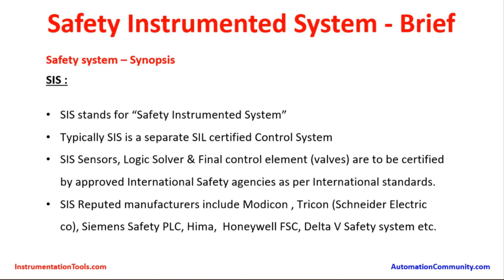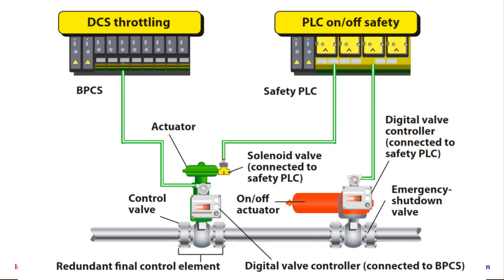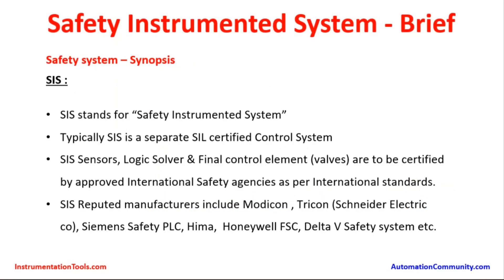I will go over the synopsis of the SIS system. SIS stands for safety instrumented system. Typically, SIS is a separate SIL-certified control system. SIL stands for safety integrity level, which we will discuss in forthcoming presentations. The SIS sensors, logic solver, and final control elements — valves — are to be certified by approved international safety agencies as per international standards. In earlier presentations, we saw the international standards by IEC, ISA, and similar agencies. They formulate the standards which are certified by another set of agencies known as safety agencies, based on which manufacturers produce and install products in the safety instrumented system.